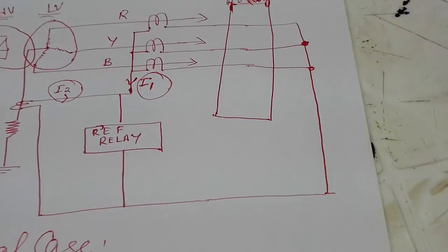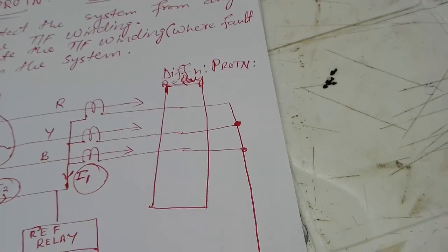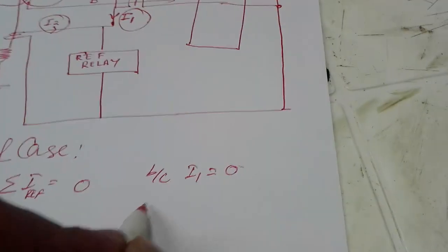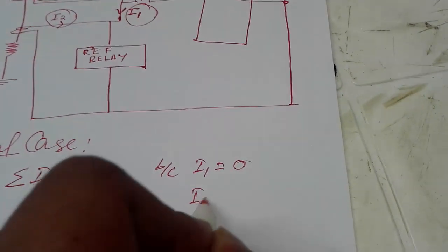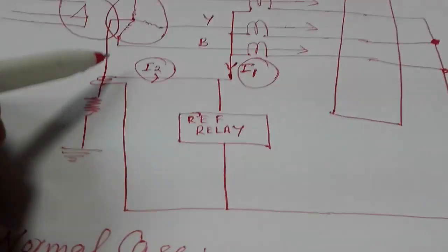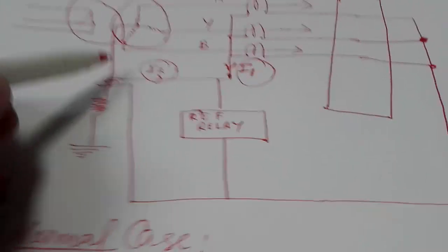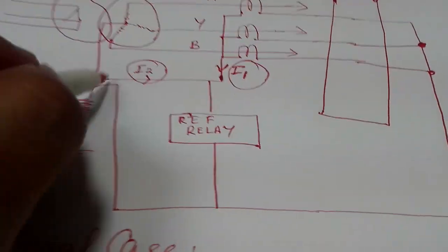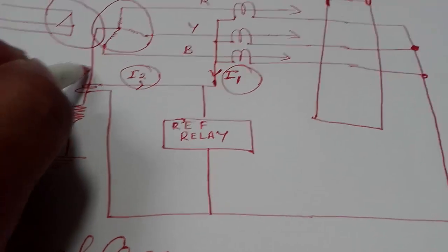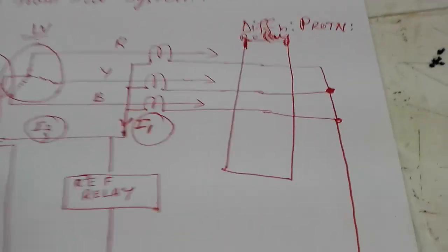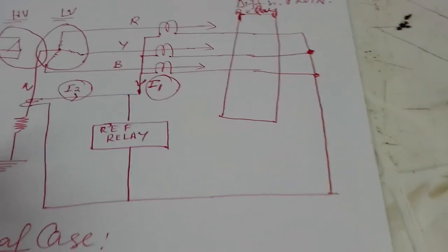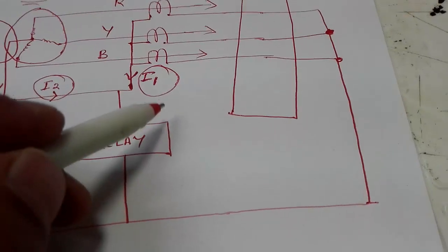I1 and I2 will both be equal to zero in normal condition. There will be no flow of current in the neutral during normal condition, so I2 will also be equal to zero. I1 is the summation of the phase currents.